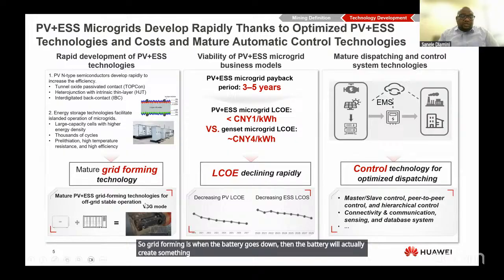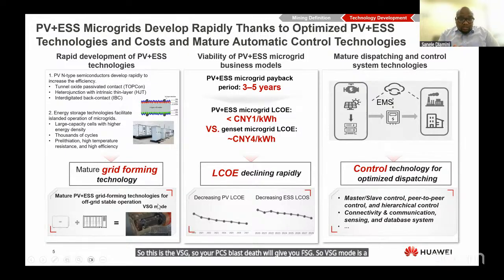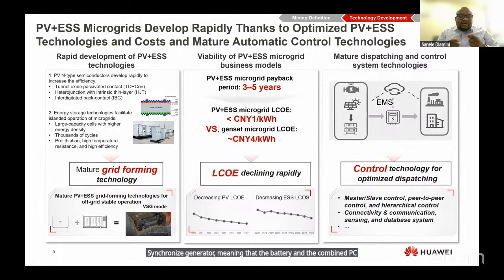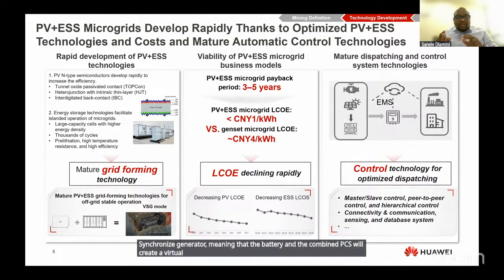Grid forming is when the grid goes down, then the battery will create something called VSG. Your PCS plus BESS will give you a VSG. VSG mode is a virtual synchronized generator, meaning the battery combined with the PCS will create virtual synchronized power.